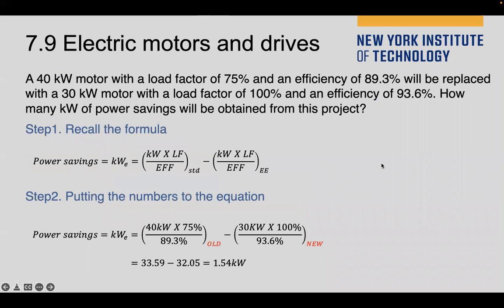So it's 7.9, about the electric motor and drive. A 40 kilowatt motor with a load factor of 75% and an efficiency of 89.3% will be replaced with a 30 kilowatt motor with a load factor of 100% and efficiency of 93.6%. How many kilowatts of power saving will be obtained from this project?